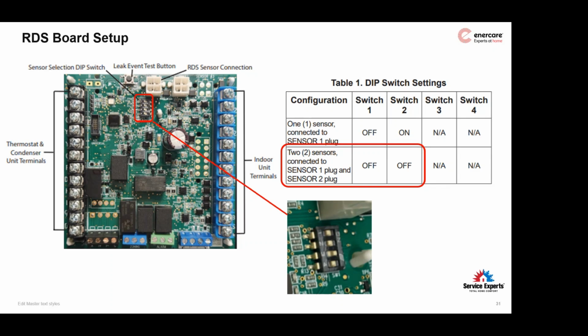On the RDS control or the equipped furnace or air handler control, you will find a small bank of dip switches that tells the control just how many refrigerant detection sensors are connected and need to be monitored. Again, this is specific to Lennox or ADP, because the other manufacturers only use a single sensor. The control board, this external one and the furnace control board, comes expecting 2 sensors. So both of the switches are in the off position, or as you can see pictured on the control, pushed to the left side.